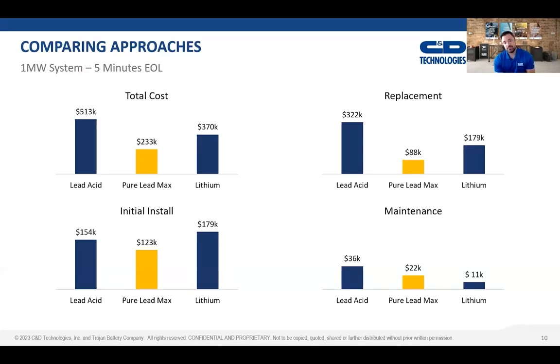For replacements, we chose to determine the replacement cycle based on the standard warranty for each technology. That puts the lead acid option at 4 replacements over an estimated life of 15 years for UPS systems, and both pure lead max and lithium at a single replacement over the life of that system.